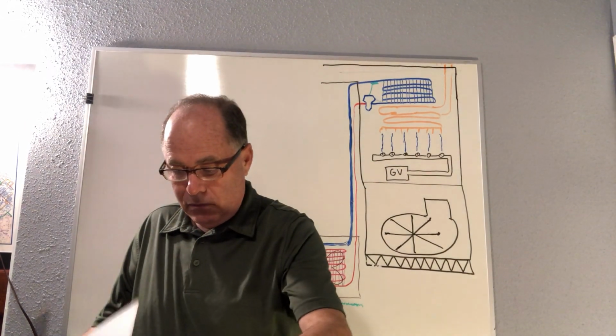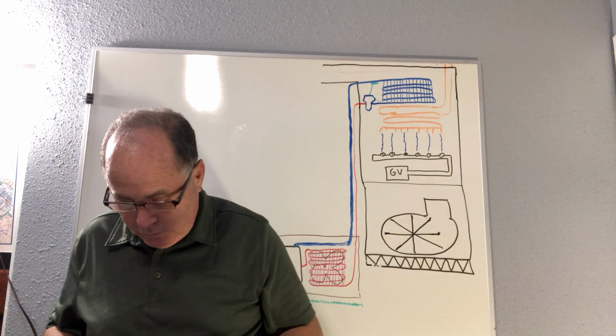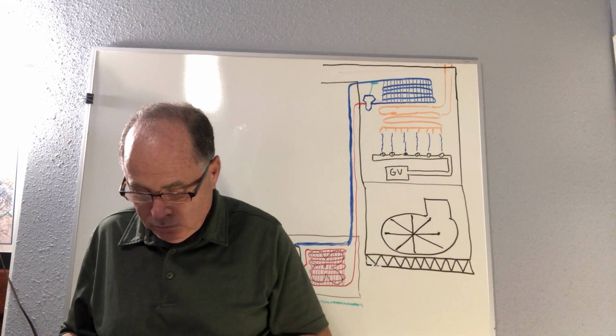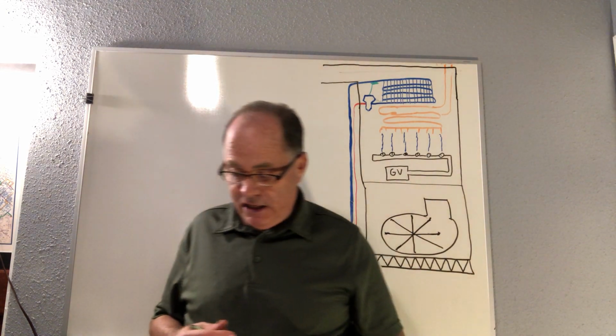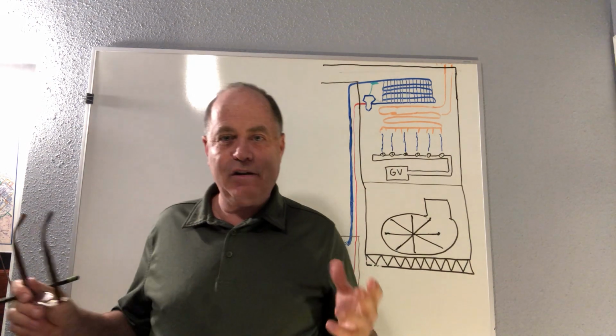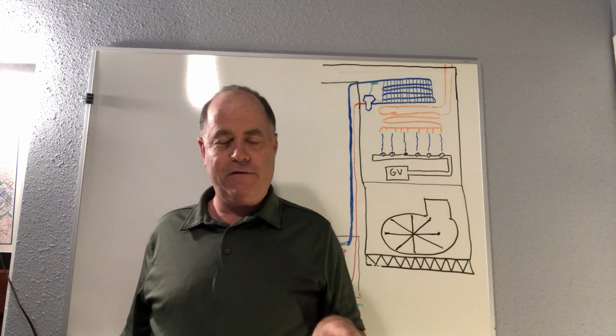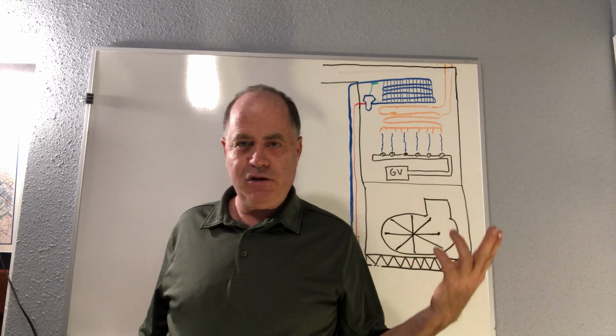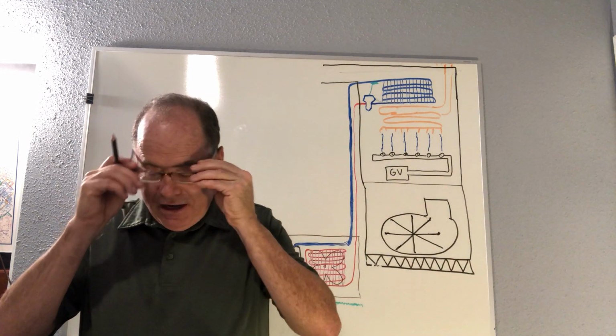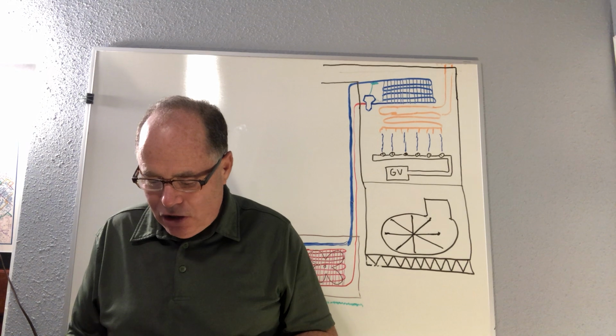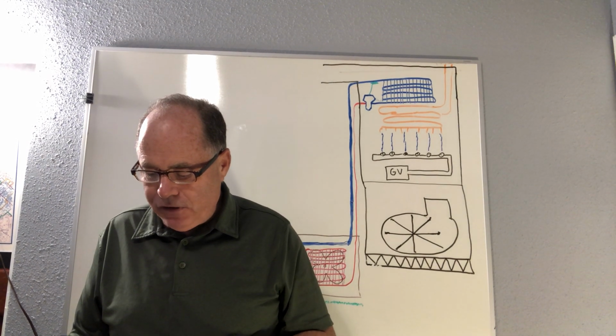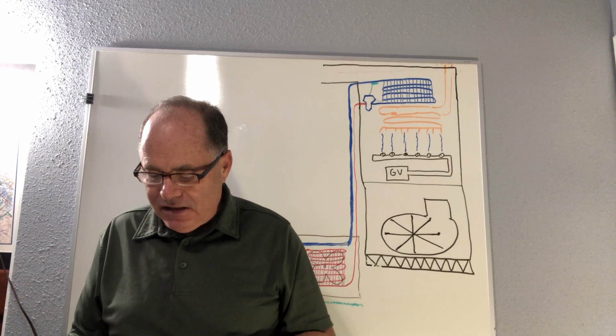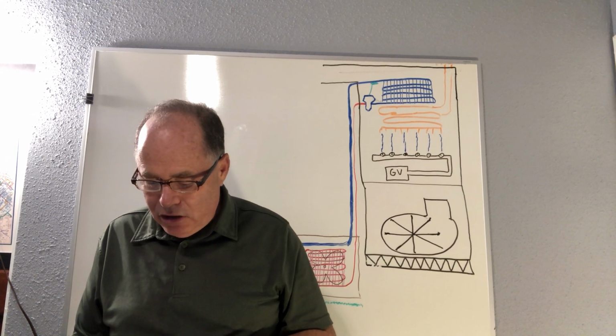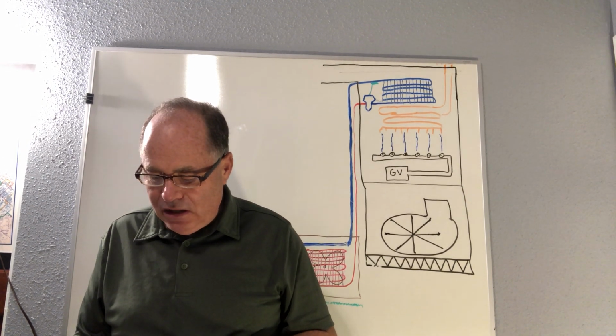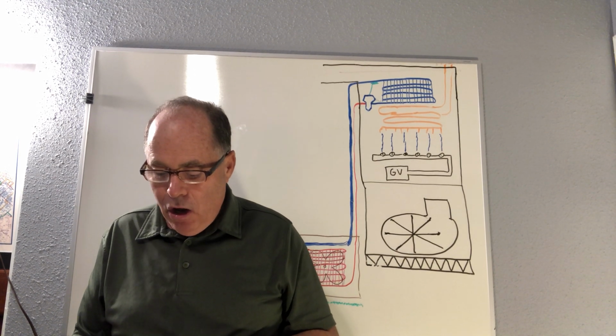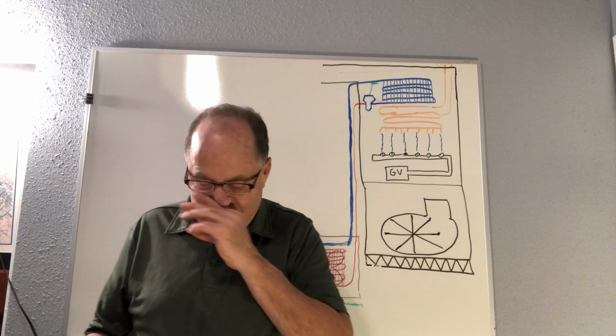All right. Now, here it talks about electric duct heaters. And actually, believe it or not, I think I found an error, not in the commentary portion of the code, but in the law portion of the code, which is exciting for me. Here it says, electric duct heaters installed with an air duct shall be listed for such use and designed for the maximum air temperature. The duct heater and fan shall be interlocked, such that the electric duct heater operates when the fan is operating. It should be written the opposite.